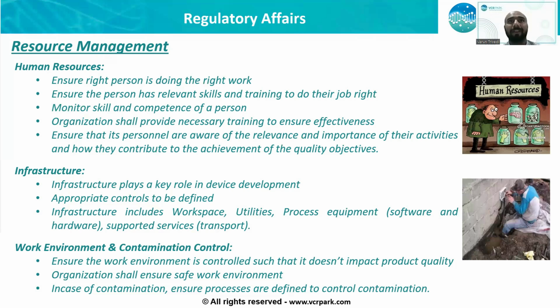Work environment and contamination control. The overall work environment shall be defined, including places where you need to have appropriate clothing. For example, when you're dealing with electronic components, you need to ensure that you are wearing ESD wrist straps or that it is ESD proof. Similarly, on contamination control, when the devices come back from the field for rework, you need to ensure that they are disinfected before you can investigate or look into them. From that perspective, work environment and contamination control is key, ensuring that the safety of the people involved is preserved. At the same time, the development activities are also defined in the right way.